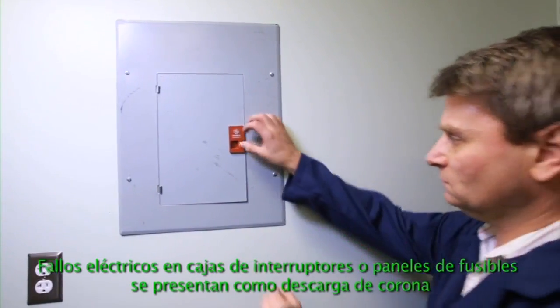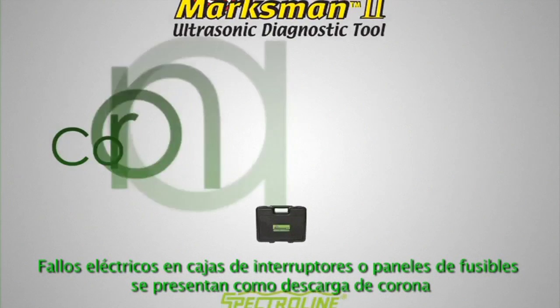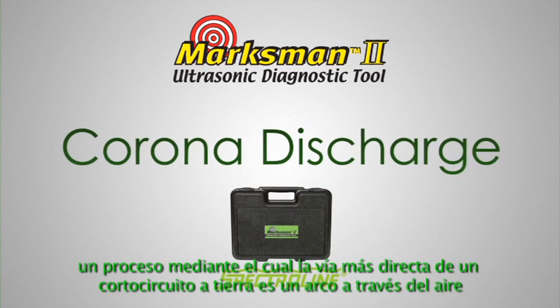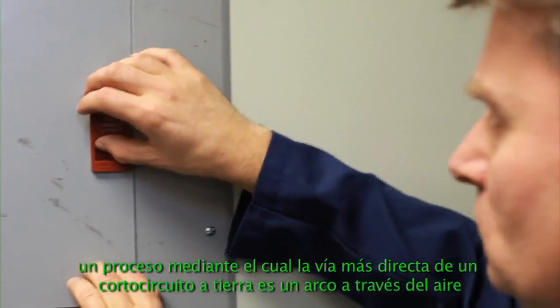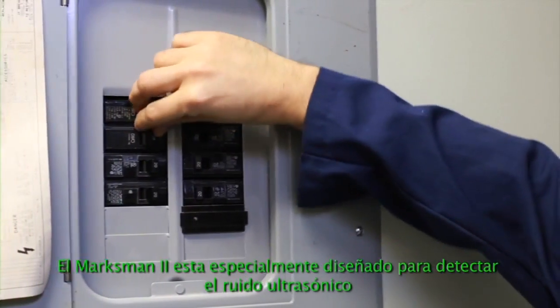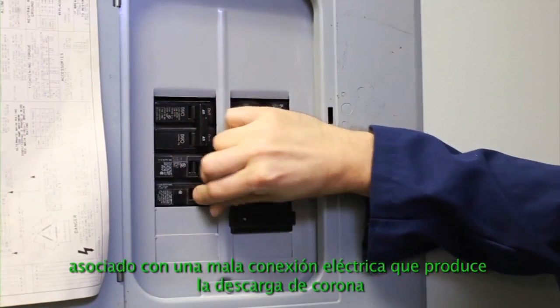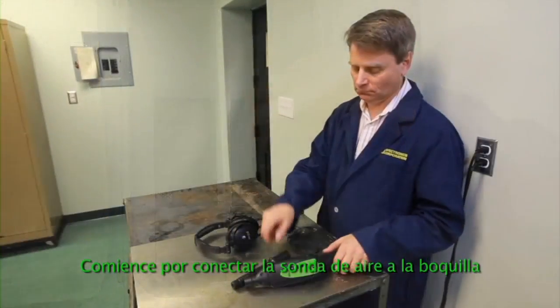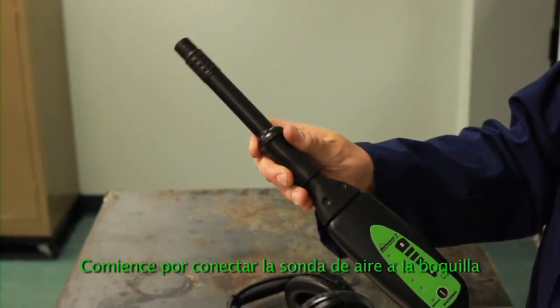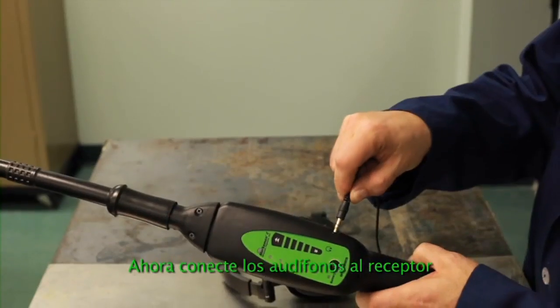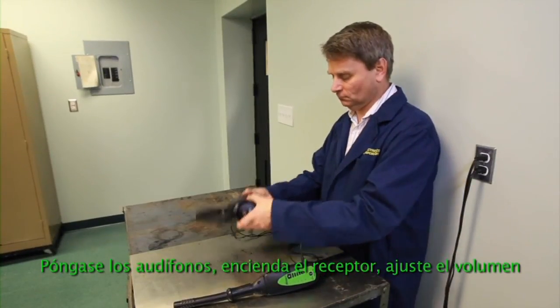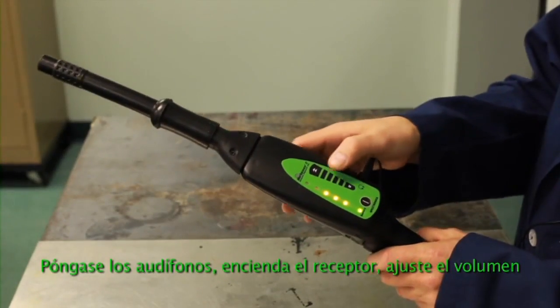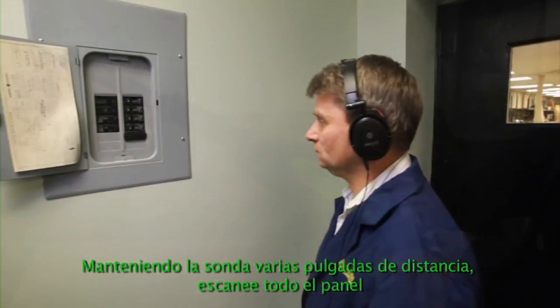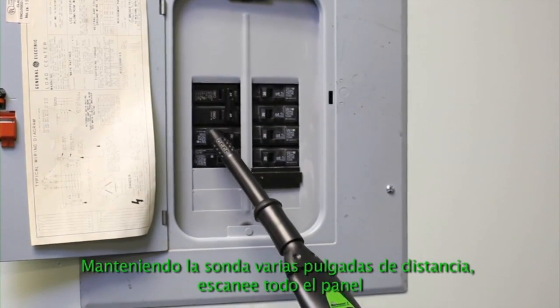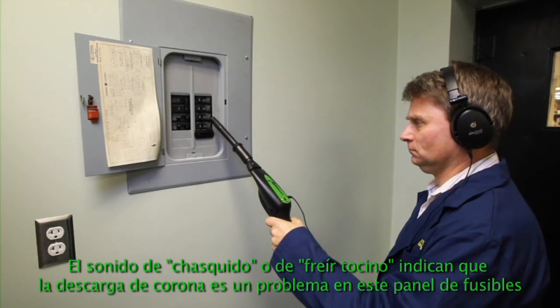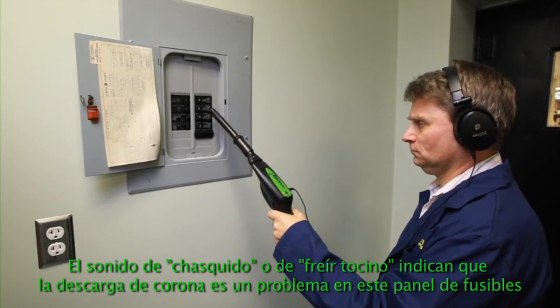Electrical malfunctions in breaker boxes or fuse panels often present themselves as corona discharge, a process whereby a short circuit's most direct pathway to ground is an arc through the air. The Marksman II is especially adept at picking up the ultrasonic noise associated with a poor electrical connection that produces corona discharge. First, attach the air probe to the nosepiece. Next, plug the headphone jack into the receiver. Put on the headphones, turn the receiver on, and adjust the volume. Keeping the probe several inches away, scan around the entire panel. The snapping or frying bacon sound is the tip-off that corona discharge is an issue in this fuse panel.